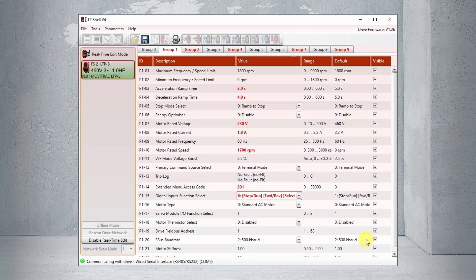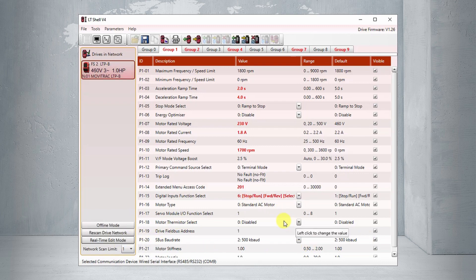Before running the VFD, remember to set the external sensor to the high state — fault sensors are active low, so if that input is low we'll get a trip immediately when trying to run. I've got a potentiometer on that input, so I'll turn it all the way up. That behaves like a switch that's on or a fault sensor in normal condition showing no fault. To trigger a fault, I'll turn that knob down until the voltage drops enough to be perceived as a low.